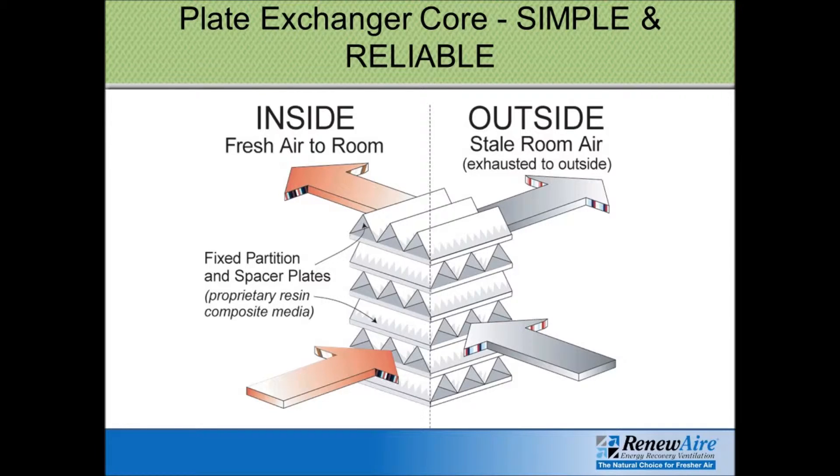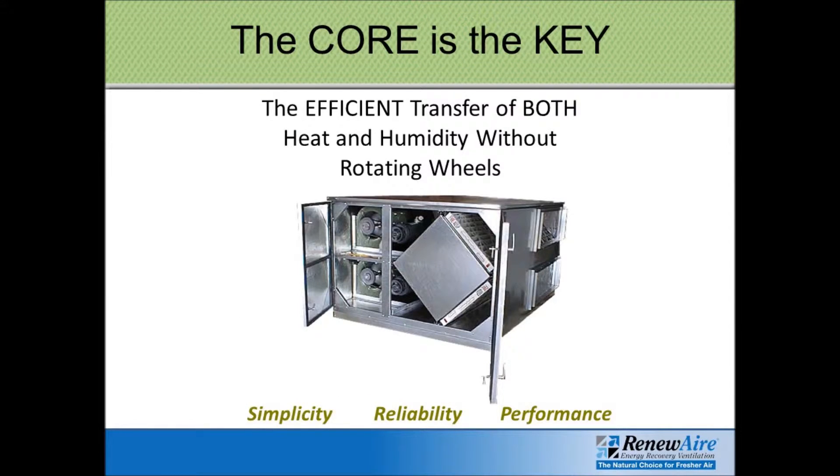Here's a close-up illustration of the RenewAire core. As you can see, it's a series of air passages, and every other air passage has the air moving from one side to the other, with the opposite every-other passage at a 90-degree angle. So the two airstreams come into the core at 90 degrees to each other, cross through the core, and as they're in the core, they transfer heat from one airstream to the other. Here's an illustration of a typical unit — the heat recovery core is a fairly large cube on one side of the unit.